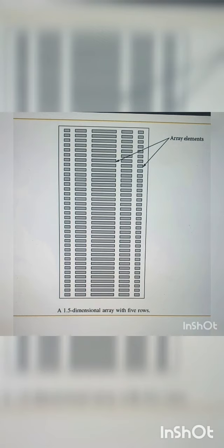This is a 1.5 dimensional array with 5 rows. The rectangular boxes you can see are the array elements. As there are only 5 rows of array elements, this is a 1.5D array with 5 rows. The number of rows of array elements can be varied according to our requirement. For a 1.5D array, dynamic focusing is achieved by adjusting the delay of returned echoes or transmitted pulses, similarly to what can be done on an azimuth plane. The areas of all rows are typically made equal to ensure equal sensitivity and input electrical impedance.